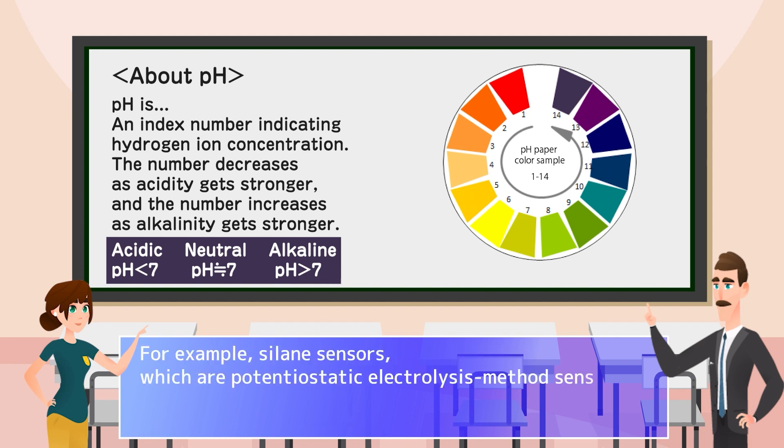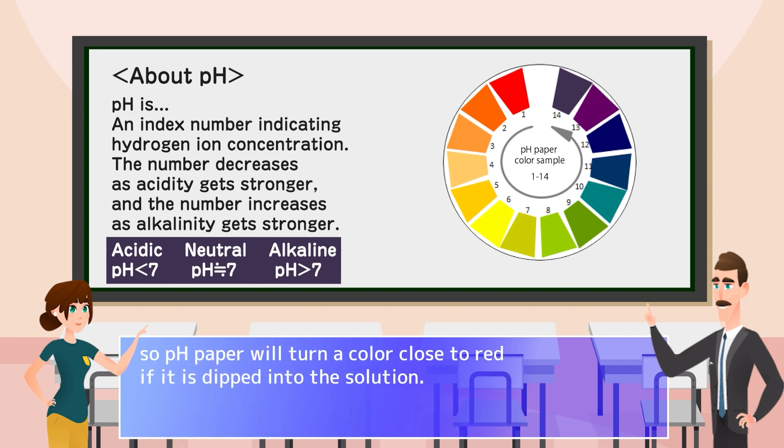For example, silane sensors, which are potentiostatic electrolysis method sensors, and phosphine sensors use a highly acidic aqueous solution called sulfuric acid in their electrolyte, so pH paper will turn a color close to red if it is dipped into the solution.